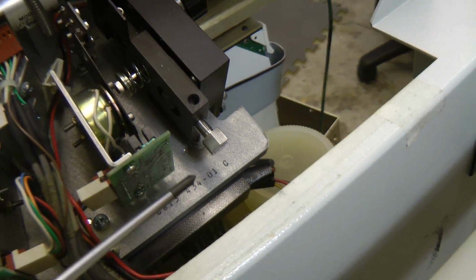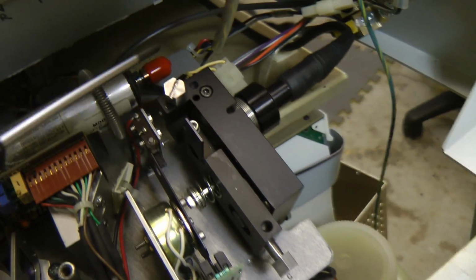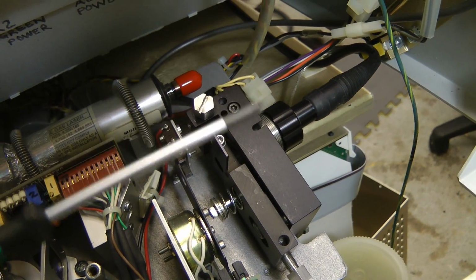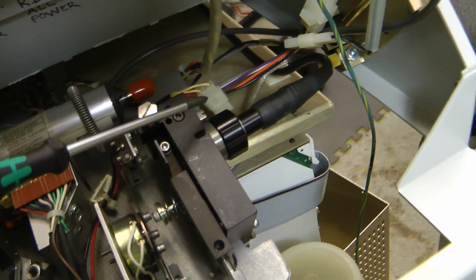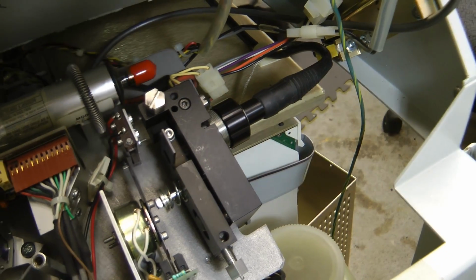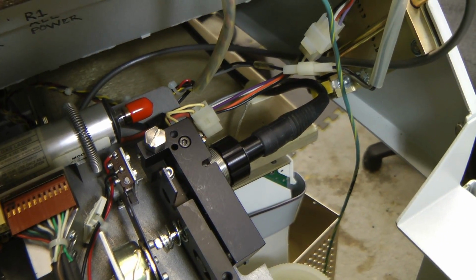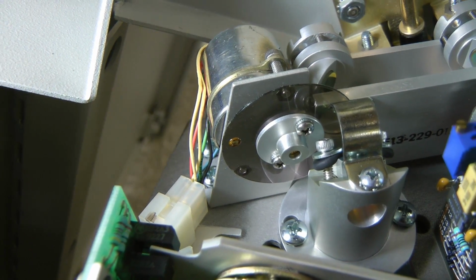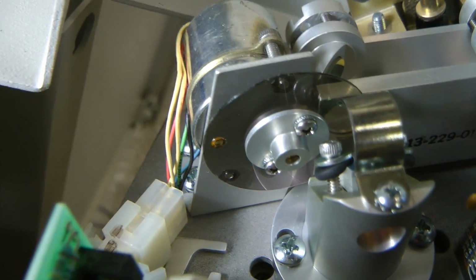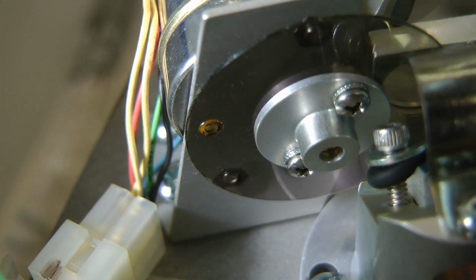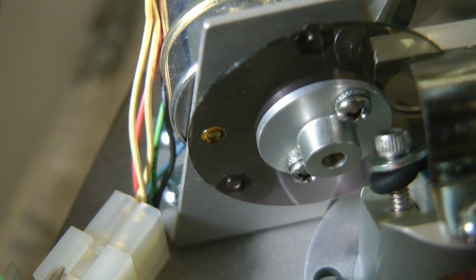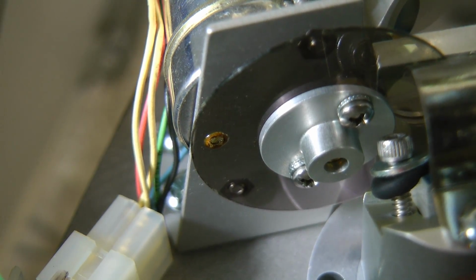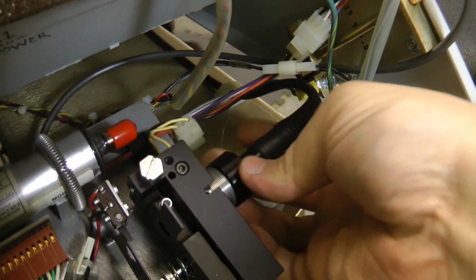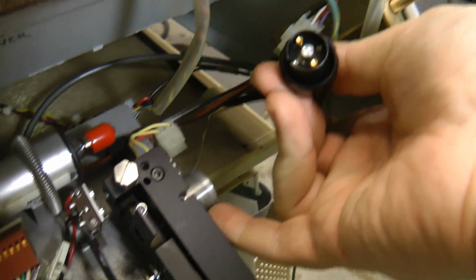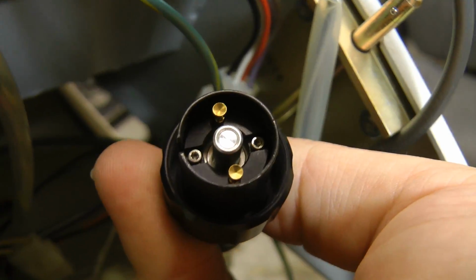A telltale sign of that are these two adjustment screws for XY, so you can move the lens slightly to align it perfectly with the input of the fiber. That doesn't look right. There's what looks like a burn mark or a melted through section on that filter. Looks like this will come off. It's just a standard fiber connector, just like on the other side.